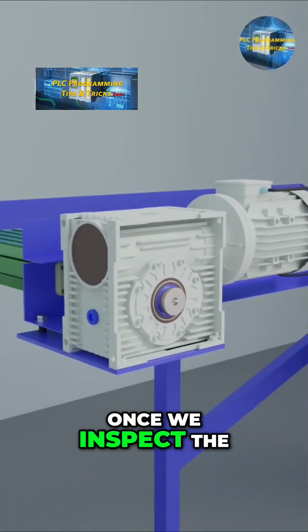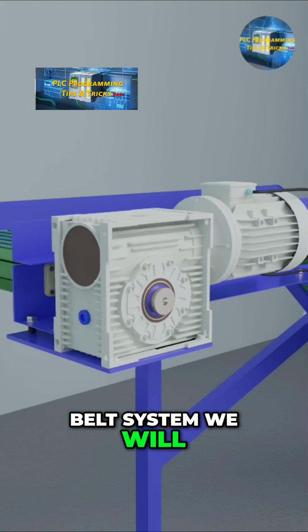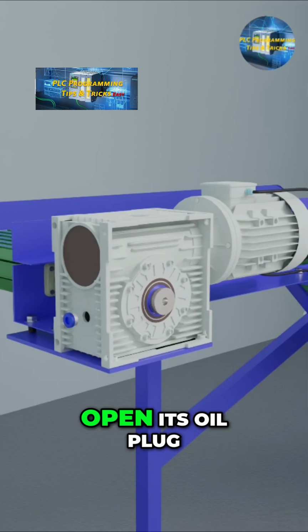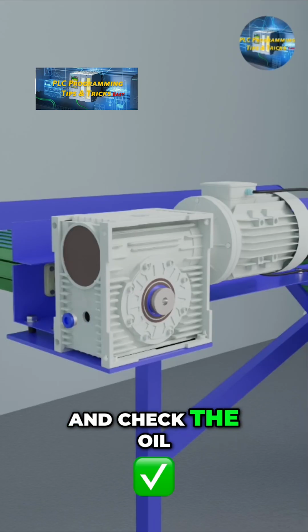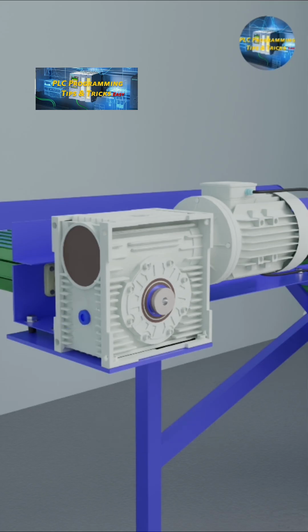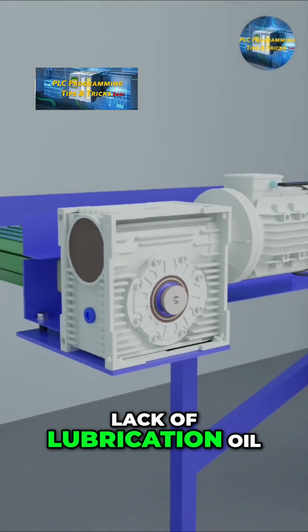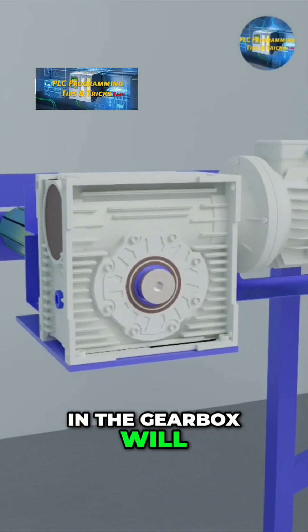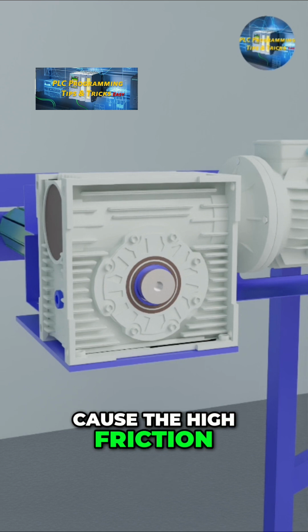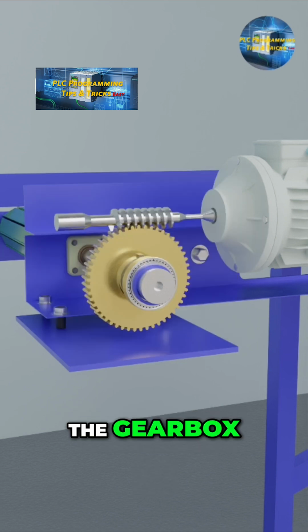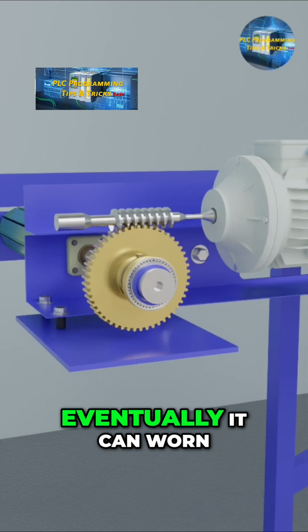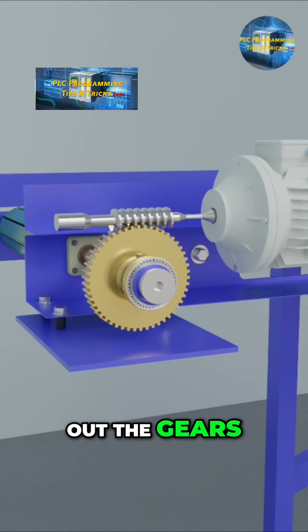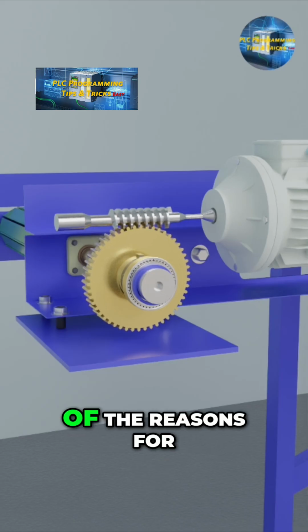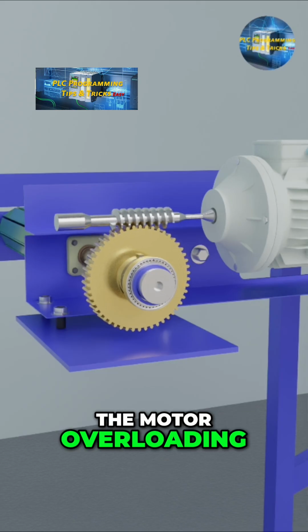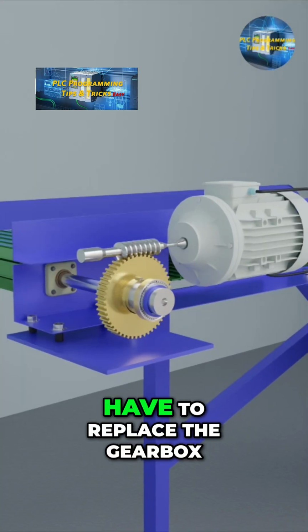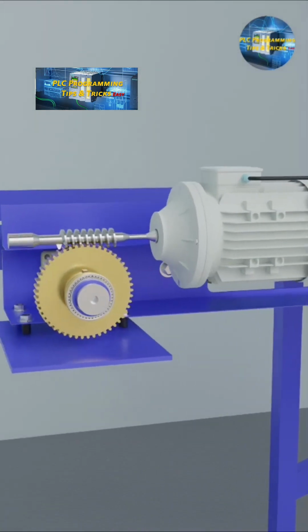Once we inspect the belt system, we will check the gearbox, open its oil plug and check the oil level in the gearbox. Lack of lubrication oil in the gearbox will cause high friction among the gears inside the gearbox. Eventually, it can wear out the gears. A damaged gearbox is one of the reasons for motor overloading. In this case, we have to replace the gearbox.